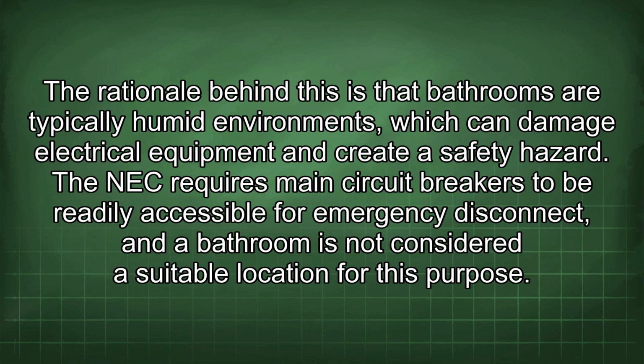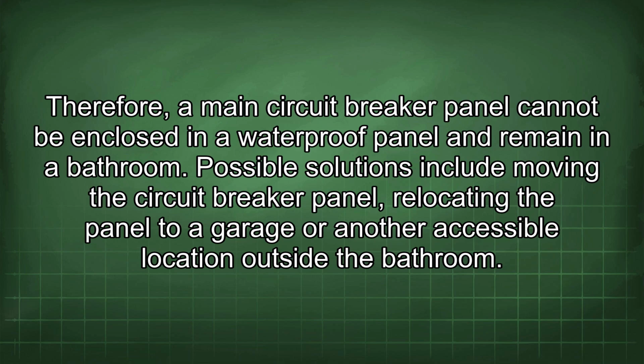The rationale behind this is that bathrooms are typically humid environments, which can damage electrical equipment and create a safety hazard. The NEC requires main circuit breakers to be readily accessible for emergency disconnect, and a bathroom is not considered a suitable location for this purpose. Therefore, a main circuit breaker panel cannot be enclosed in a waterproof panel and remain in a bathroom.